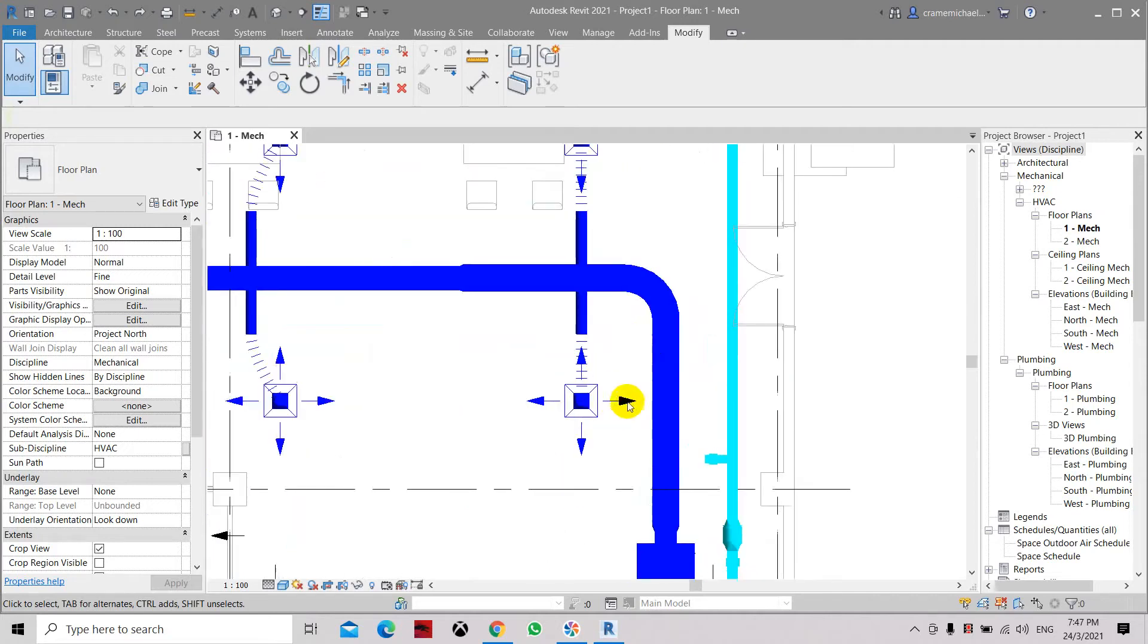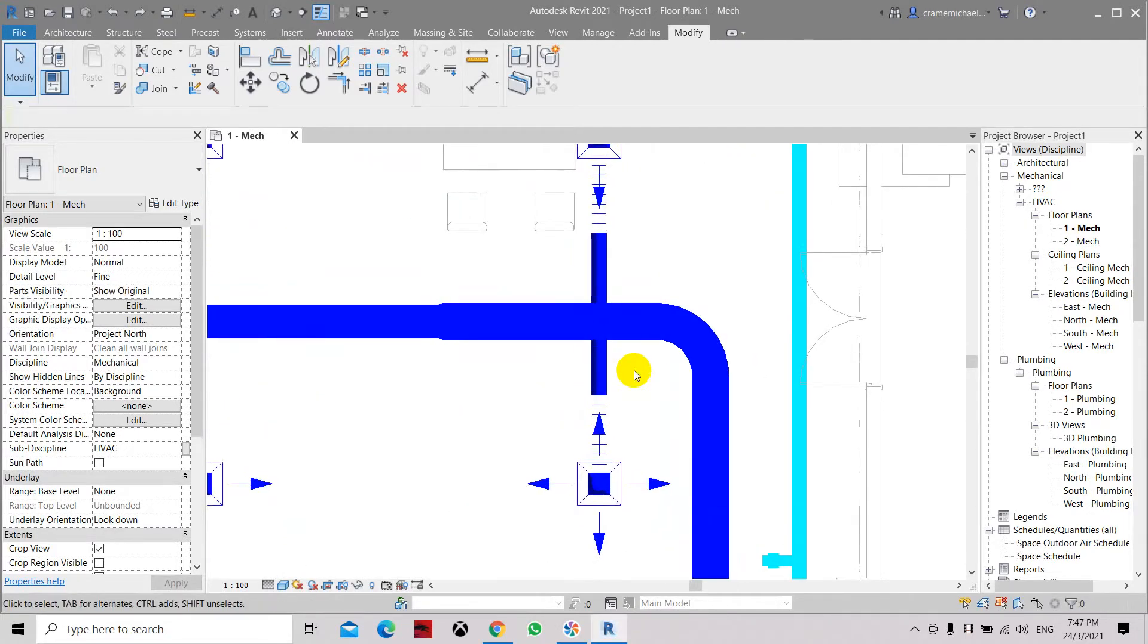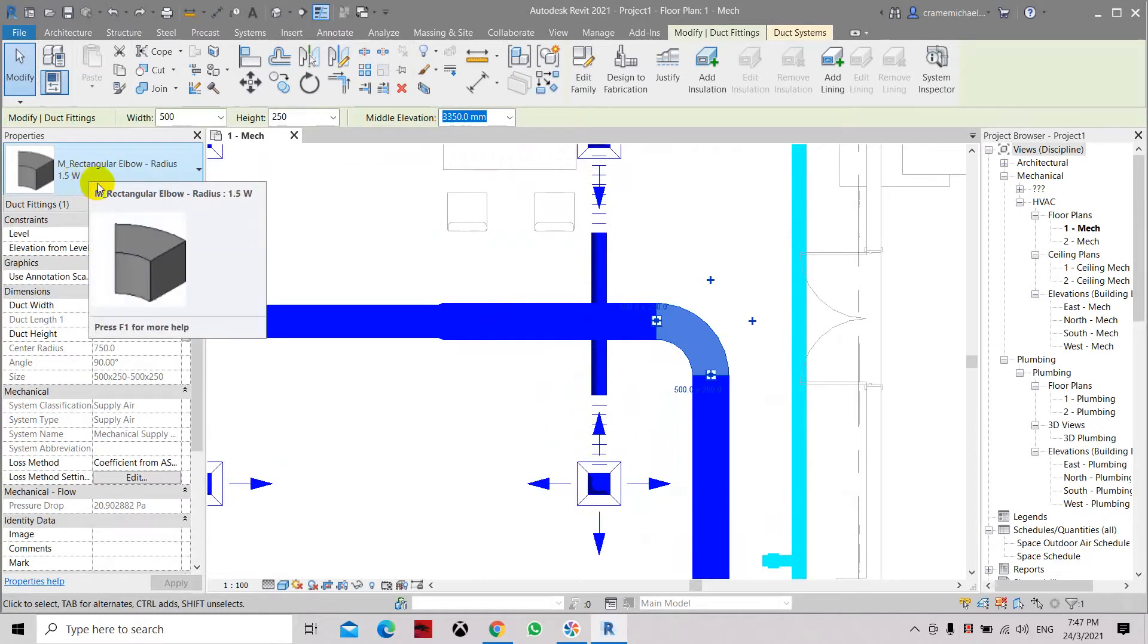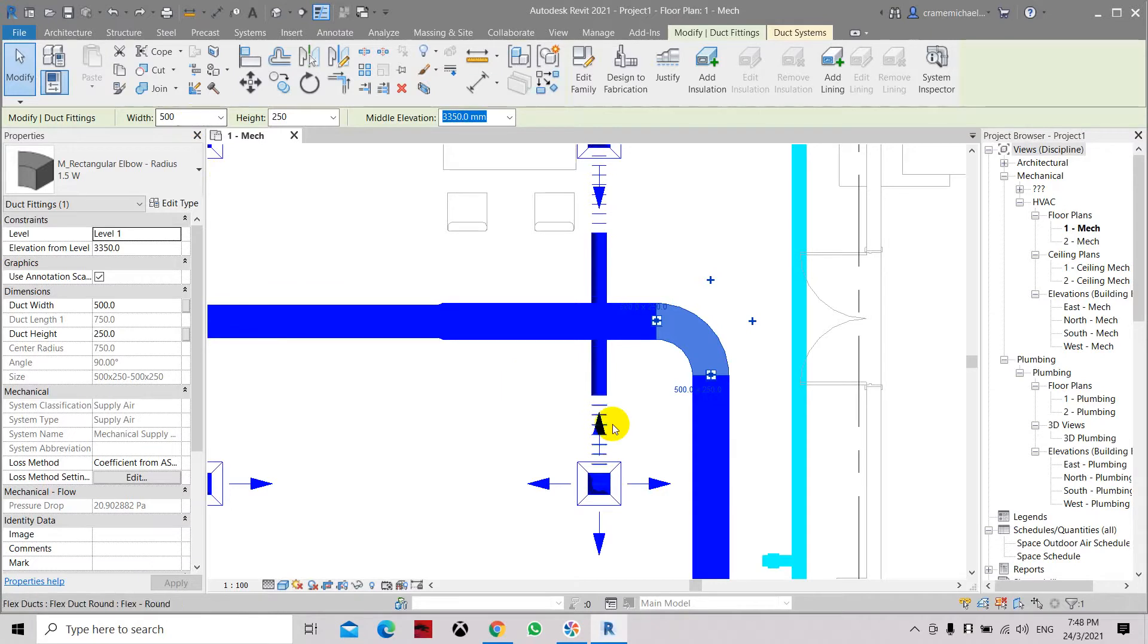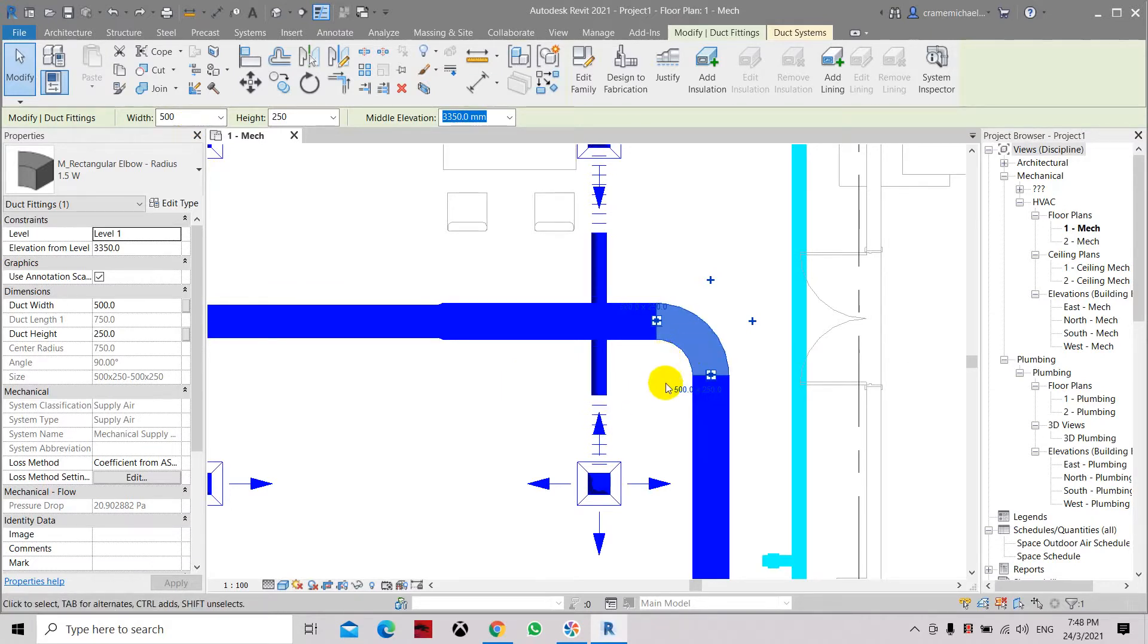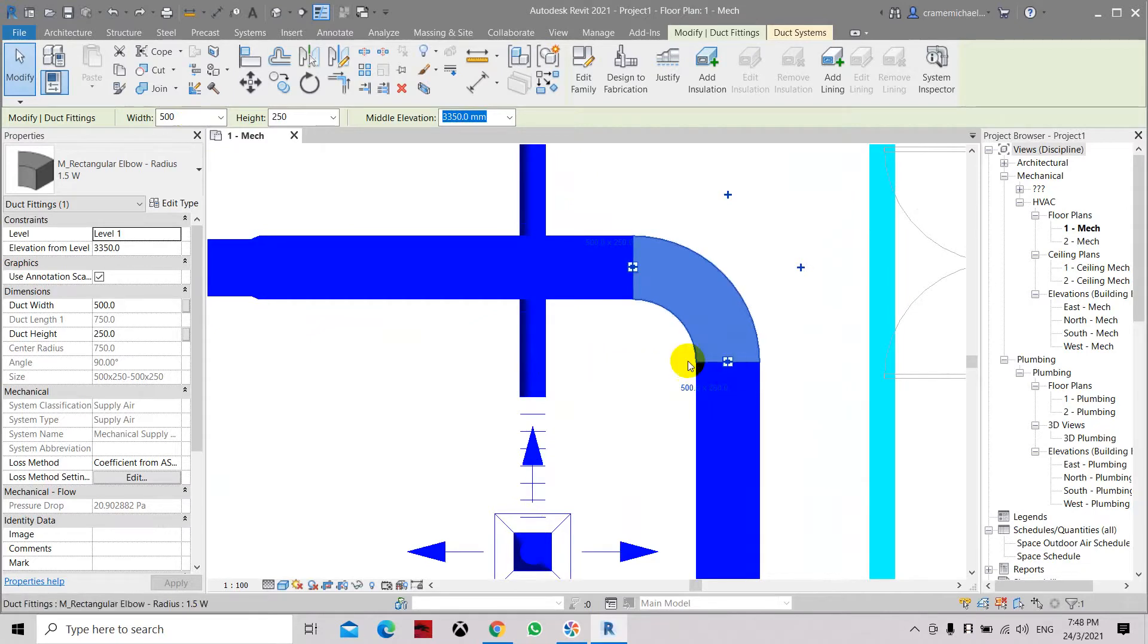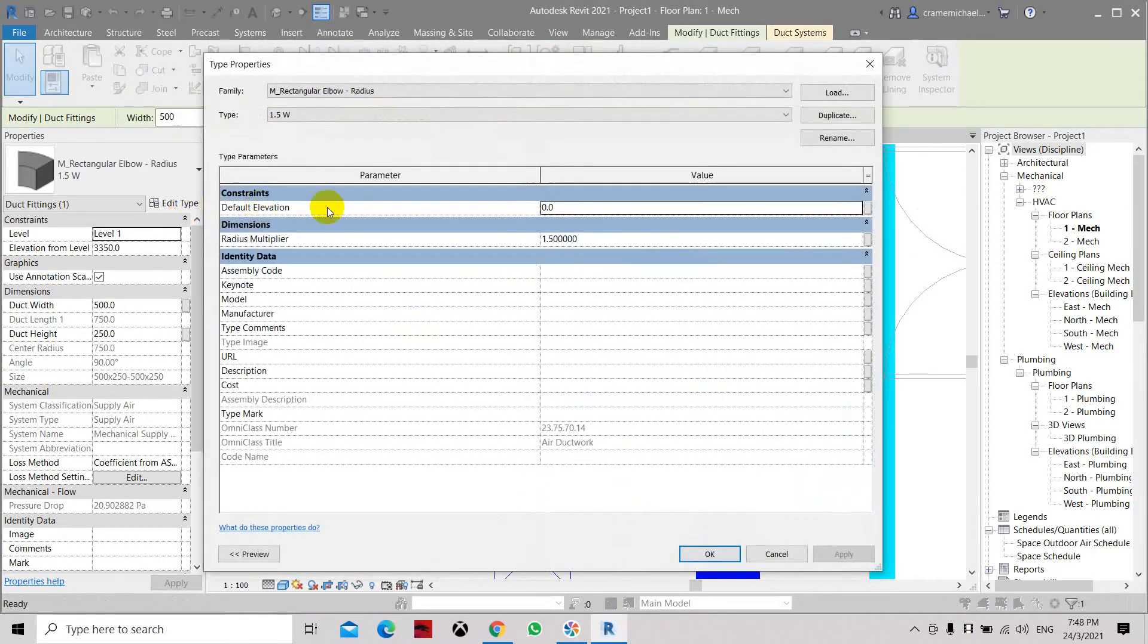To change the duct elbow radius if you are new in Revit: Here we have a duct fitting where the radius is about 1.5 of the width and our duct size is 500. So 1.5 of the width is about 750. Starting from here it's 750, minus the radius is about 500, so it's almost the same as the width of the duct. To reduce it, let's set it here.